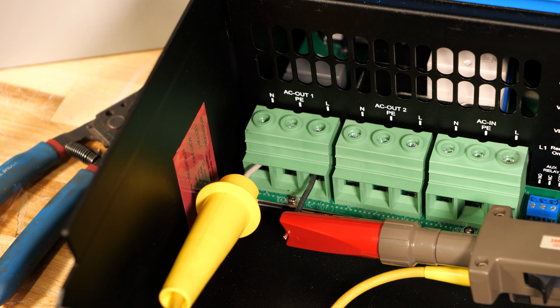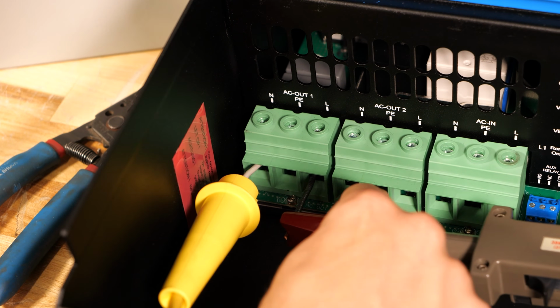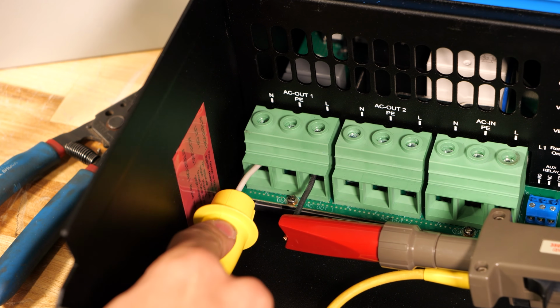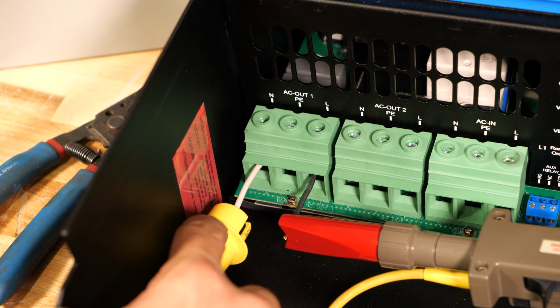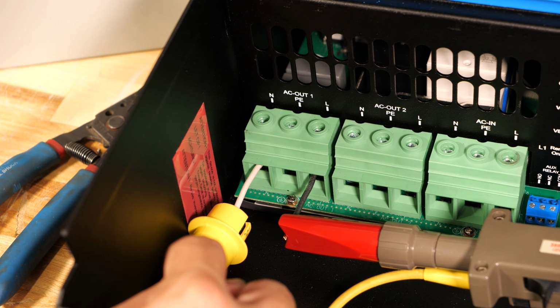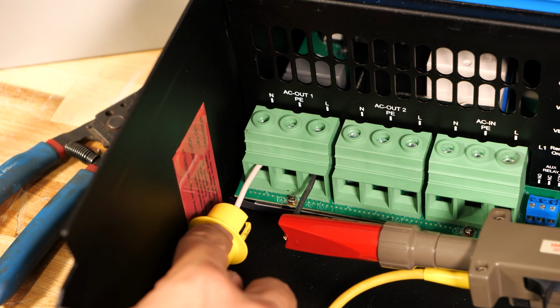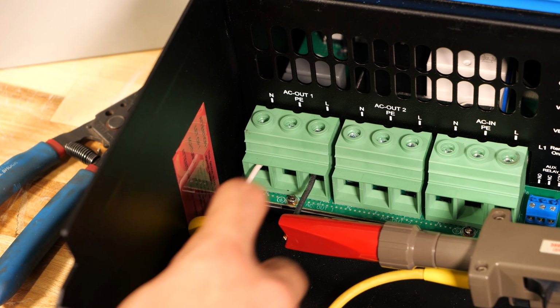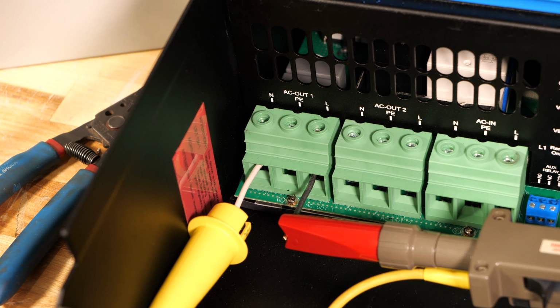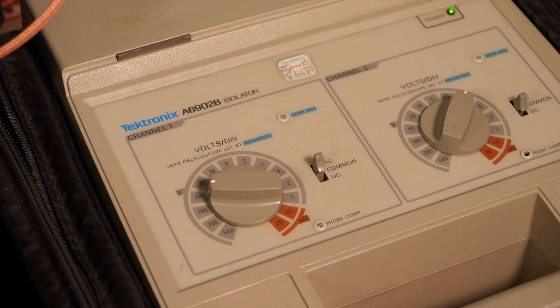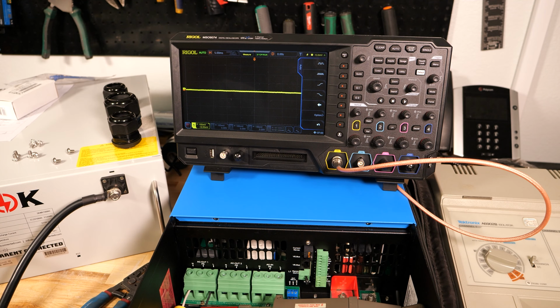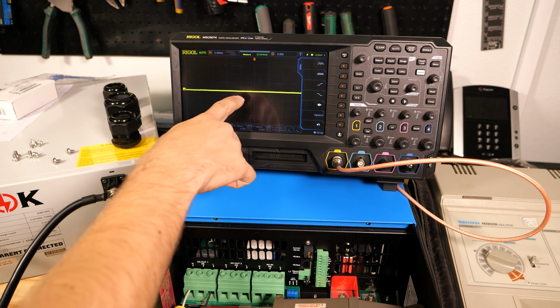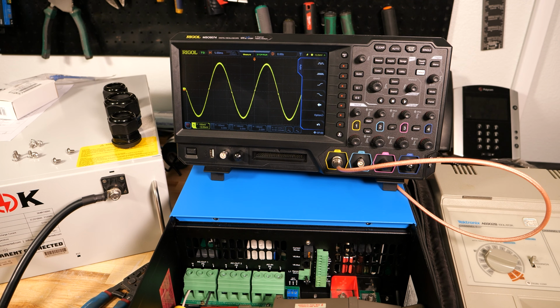So as you see here, I've got my 3000 volt differential probe connected on, with a little piece of solid wire in that terminal strip going to the probe. Since this is a 100% differential probe, I'm fine clamping the ground reference to the neutral out of the inverter. I currently have the differential probe set at 50 volts per division, AC coupled into the oscilloscope. Let's power on the inverter and see the sine wave come up.